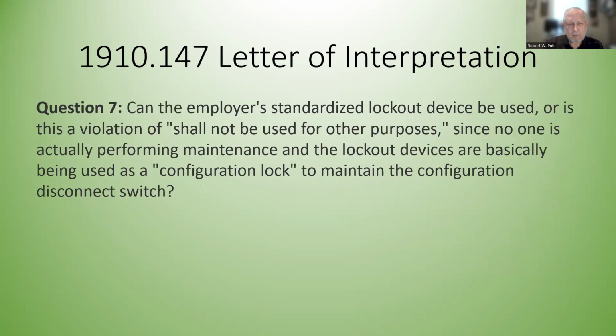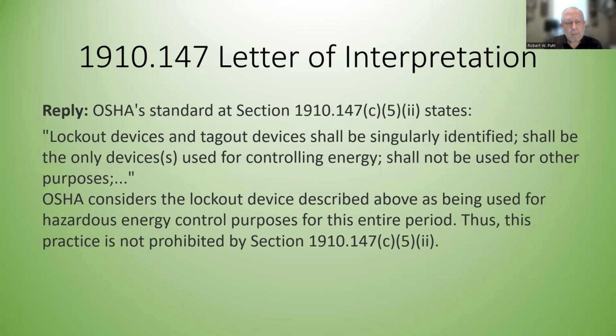So, Scenario 4. Okay, so question 7. Can the employer's standardized lockout device be used, or is this a violation of "shall not be used for other purposes," since no one is actually performing maintenance and the lockout devices are basically being used as a configuration lock to maintain the configuration of the disconnect switch? Now, this is a pretty intelligent question, because it's a little bit of a gray area. But the answer is, lockout devices and tagout devices shall be singularly identified, shall be the only devices used for controlling energy, and should not be used for other purposes. OSHA considers the lockout device described above as being used for hazardous energy control purposes for this entire period. Thus, this practice is not prohibited by the section.